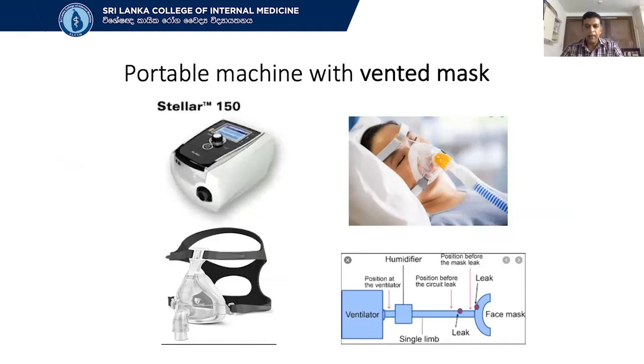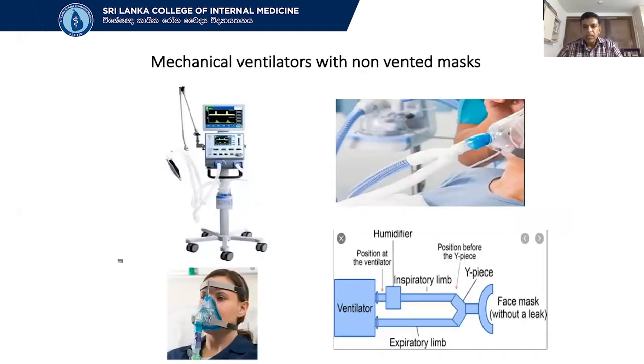Now, this is what I meant by a single limb. You see on your bottom right an NIV generator with a humidifier, then a filter, then the vented mask with a single limb. You can clearly see there is leaking from the mask, which goes into the surrounding environment in a positive patient. This is considered aerosol generation, and we need full PPE to manage these patients. But in most ICUs now, patients on NIV use what we call a dual limb circuit with a non-vented mask. Since there is an expiratory limb, you don't need special holes for the expiratory air to leak out, and these are safe closed systems. We still use full PPE, but these are safe.